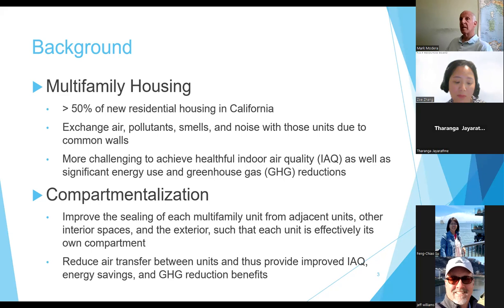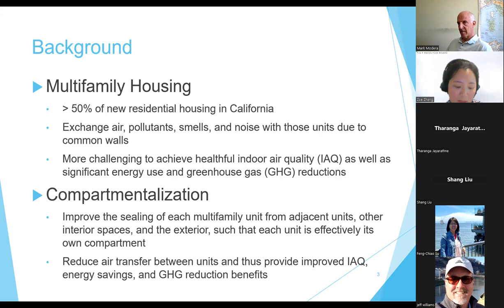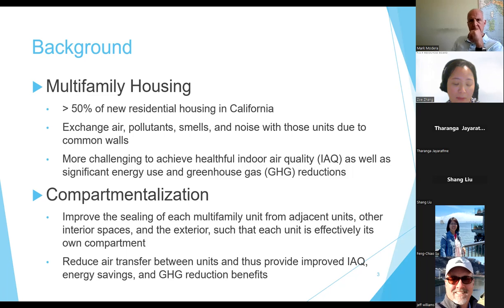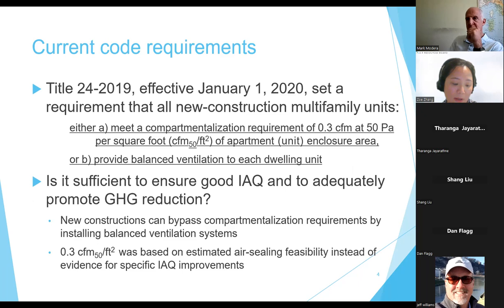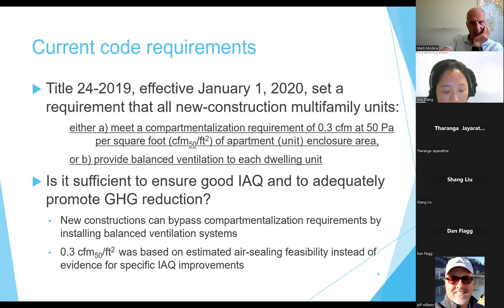Achieving good indoor air quality as well as significant energy savings is more challenging in multifamily buildings. Compartmentalization, or increasing air tightness between units, is a process to improve the sealing of each multifamily unit from adjacent units, other interior spaces, and the exterior, such that each unit is effectively its own compartment. It can reduce air transfer between units and thus provide improved indoor air quality, energy savings, and GHG reduction benefits. Therefore, Title 24 2019, effective January 1st, 2020, required that all new construction multifamily units either meet a compartmentalization requirement of 0.3 CFM per square foot or provide balanced ventilation to each dwelling unit.